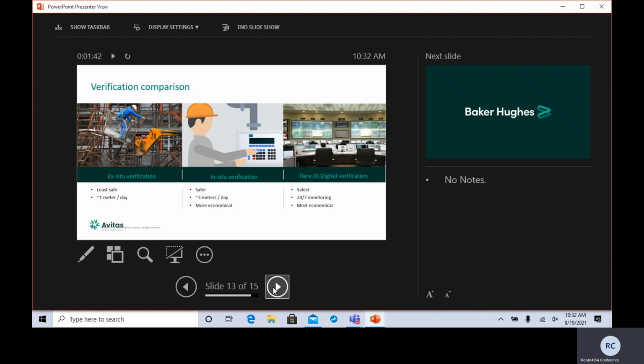The next step is digital verification. So this is where we install a Flare IQ box, we connect it all, and from the safety of the control room, our engineer can do the verification on demand. Provide you with the full report that's required, but there's no need to even go into the operating unit. So obviously this is the safest. We joke around that our engineers can go in khakis and a polo like Jake from State Farm, and do a verification. But in reality, they're showing up with their FRs in case there's a problem and are ready to fix anything. For myself, I think that's great.